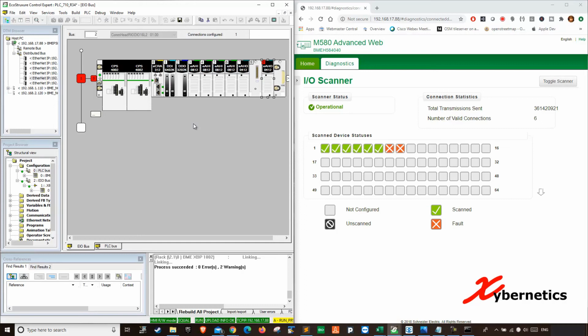One more thing before I close this, I would like to talk a bit about the AMO card and the BMX AMO card, the one with only 4 to 20 milliamps, and the AHO 0412 card. So the key thing is that if you don't really need HART, or if there's no plan in the future to add HART transmitters, this doesn't really make any sense to pay that extra money to buy an AHO card, right? You know what I'm saying?